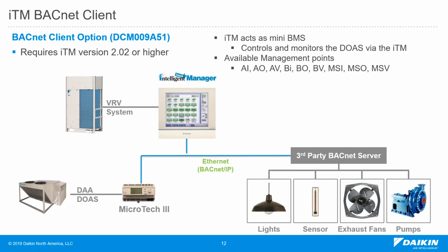When we talk about the ITM BACnet client, as most of you already know, the ITM client is a license that can be added to the Intelligent Manager, and that can happen at any time during the project cycle. So after commissioning the project, you can go back and add the client function, and from there you can add any other equipment to the ITM. It could be a lighting system, exhaust fan, any sensors, any equipment in the building can be integrated into the ITM over BACnet IP. And we teach how to do that commissioning in the ITM BACnet commissioning class.